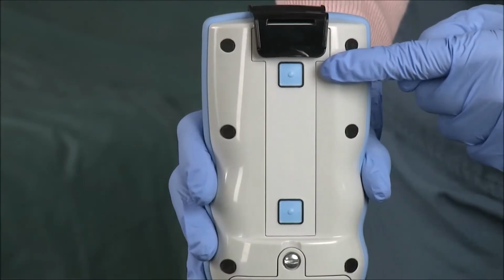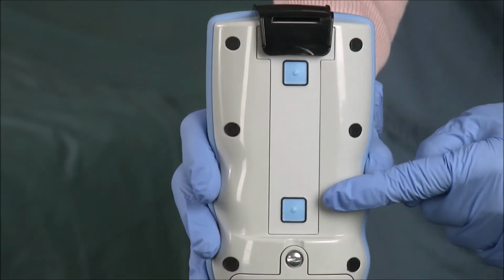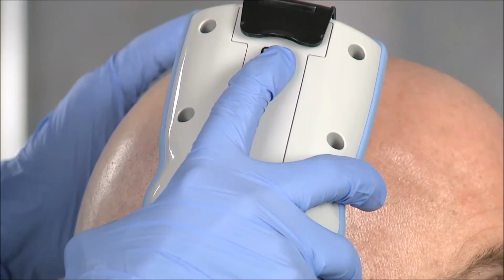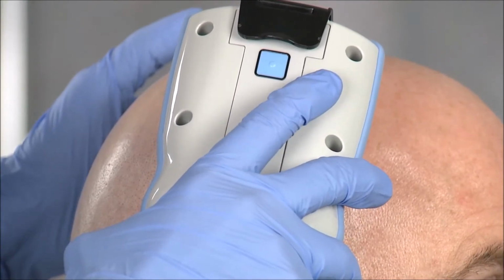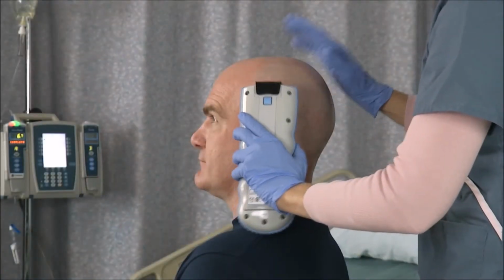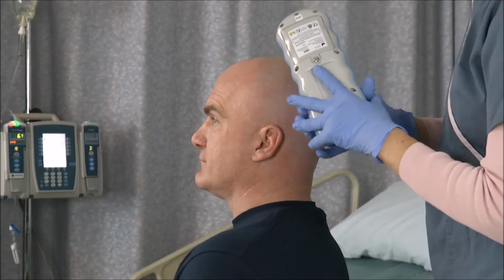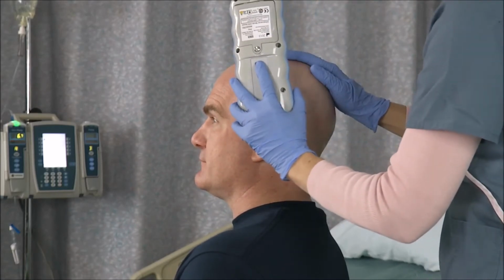There are 2 measurement buttons located on the back of the infrascanner. Either measurement button may be used for any given measurement. However, depending on the location being measured, the operator may find it easier to invert the scanner. It is recommended to hold the infrascanner with fiber optic tips up for the frontal and parietal measurements, and then invert the infrascanner with fiber optic tips down for the temporal and occipital measurements.